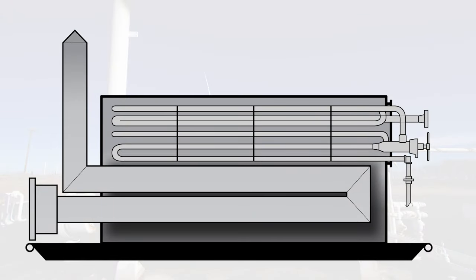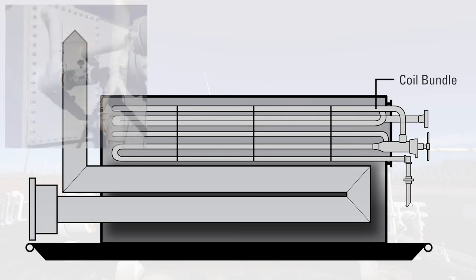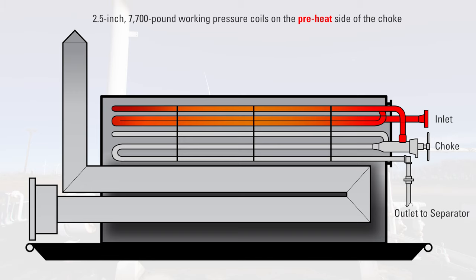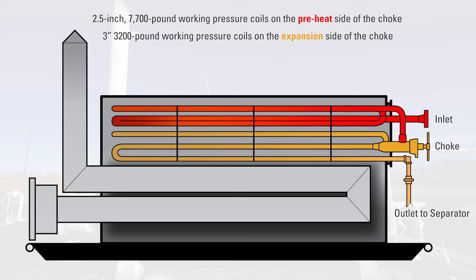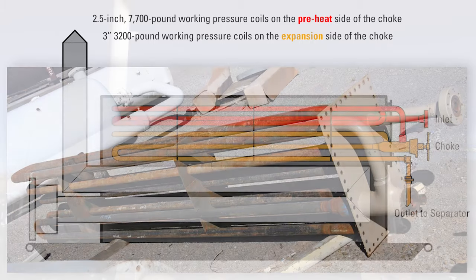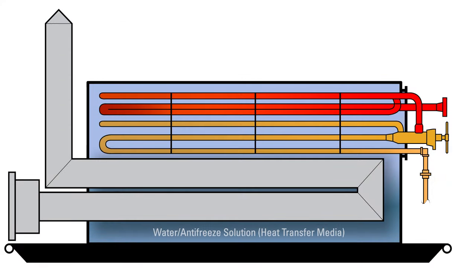The GPU has a coil made up of continuous passes of piping. The tag here tells us it's made up of two and a half inch, 7700 pound working pressure coils on the preheat side of the choke, and three inch, 3200 pound coils on the expansion side of the choke. These coils are immersed in a water antifreeze solution that acts as a heat transfer media, and that solution is heated by a fire tube contained in the heater section of the GPU.